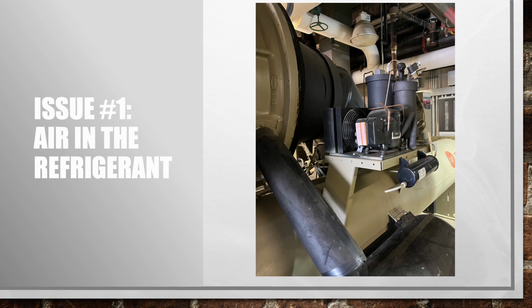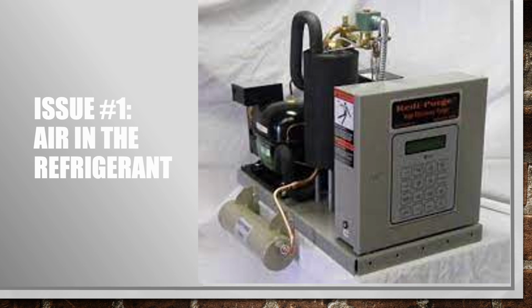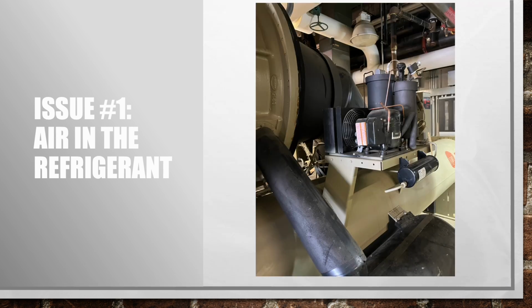If you're not in a hurry, you can just turn your purge on all night, turn the alarm settings up in there and just run it overnight and see what it does the next day if you want to try that too. But it's really easy just to vent off the top into a drum. So that's usually what I do, just to get the thing online so the customer can get their machine operating again. So if you did end up having air in the system, then you need to look into why you got it in there in the first place.